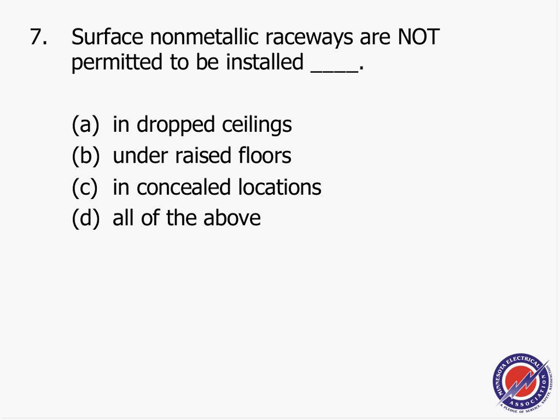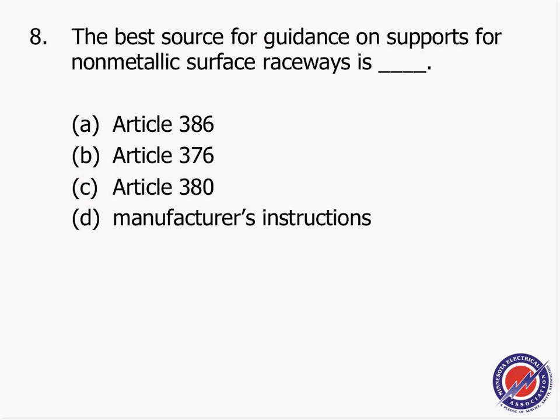Oh, number 7. Number 7: surface non-metallic raceways are not permitted to be installed in dropped ceilings, floor, all of the above, in concealed location. These raceways are not meant to be concealed. I know you can go through the partition, guys, but that's not concealment. Complete concealment is not what they're meant for.